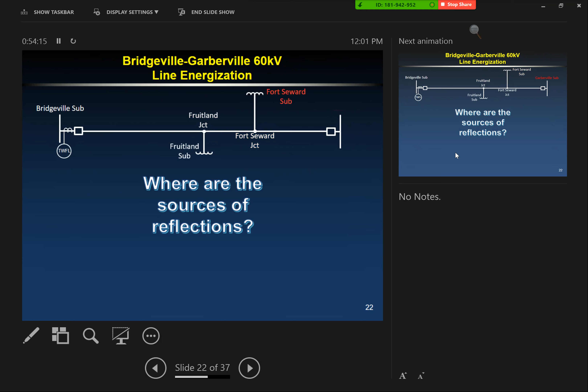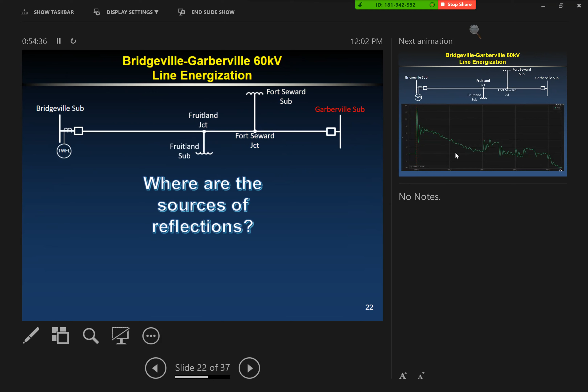Fruitland sub—you get a bank, which has a higher characteristic impedance on the line, right? So that's a source. Fort Seward Junction, another change in characteristic impedance. Bank at Fort Seward sub, and then Garberville sub, which has multiple lines leading into it. Actually, in this case, only one line, but it has another bank, so it still looks like a lower characteristic impedance on the line. It could also be open, like on a line energization test, or testing into a fault manual test.